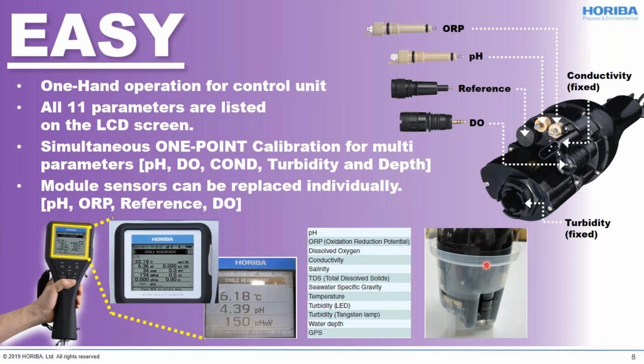The common troublesome issue for multi-parameter measurement is calibration. The U-50 allows you to use just pH4 solution for pH, dissolved oxygen, conductivity, turbidity, and depth calibration. It comes with a special beaker like this for calibrating these parameters at one time. In case an electrode doesn't work anymore, you can replace each sensor easily. These sensors are removed easily, and there is no need to change the whole probe unit.